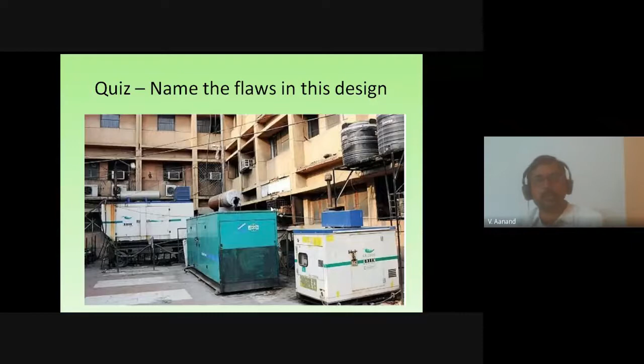Most importantly, you being architects, you know this is a flat surface. If leaves fall on the generator top and rain falls on it, the leaf starts decaying, settles on top of the generator, slowly rusts the top cover, and eats up the enclosure, allowing water to percolate inside. This is a major risk. So even if a flat surface is provided, there has to be a slope on top to ensure water doesn't enter and leaves fall down, so dust and water don't interact and eat up the generator enclosure surface.